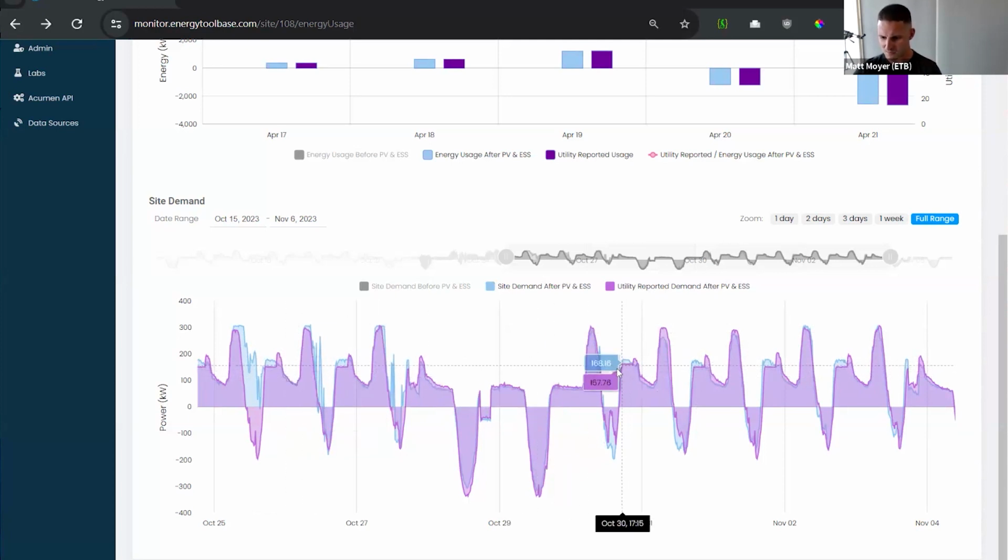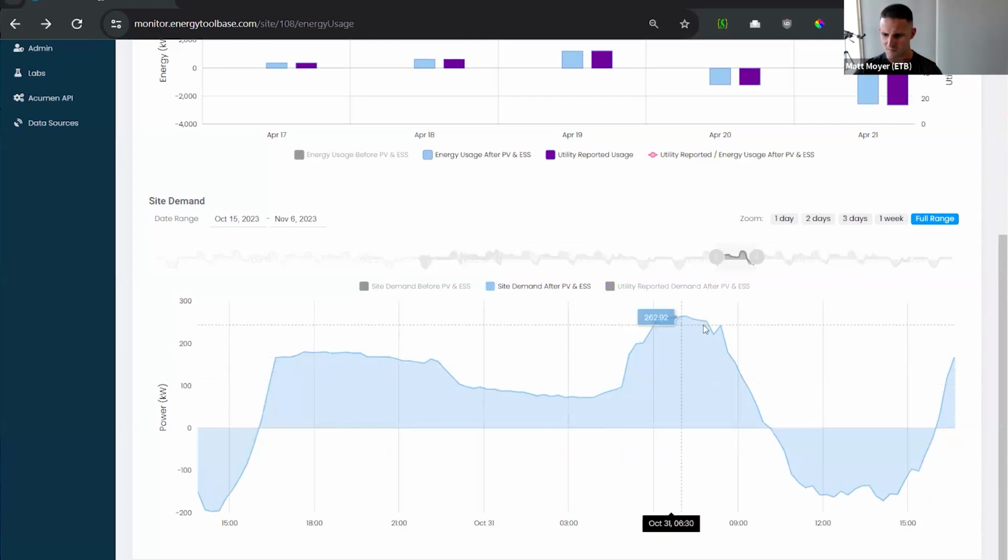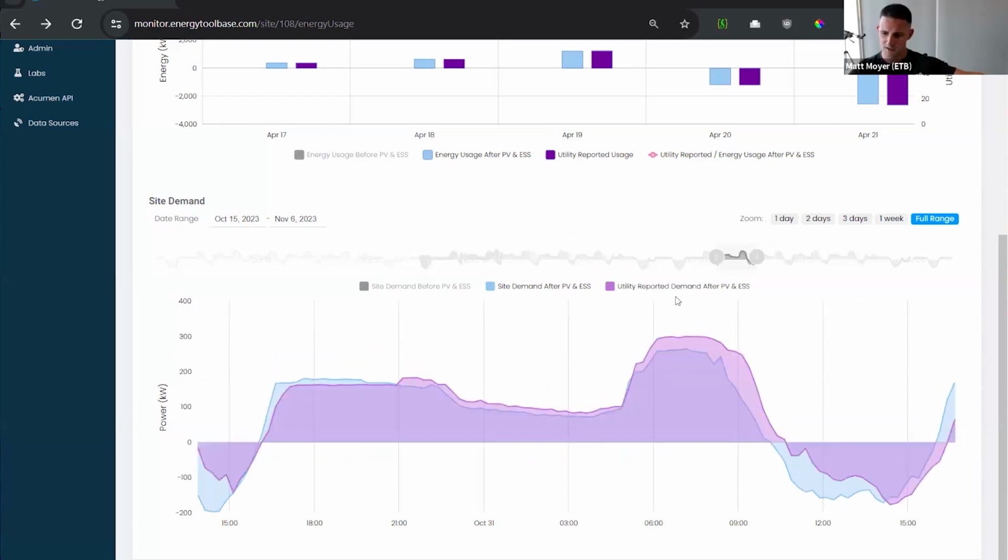You would get a day like this, where this is what's actually happening at the site. The utility doesn't have the actual data. It backfills it with historic data. And it picked days where the usage historically was significantly higher, to the point where it was creating those new spikes.